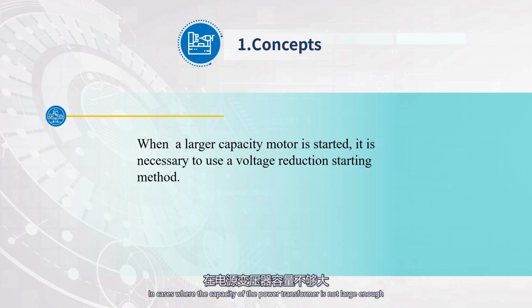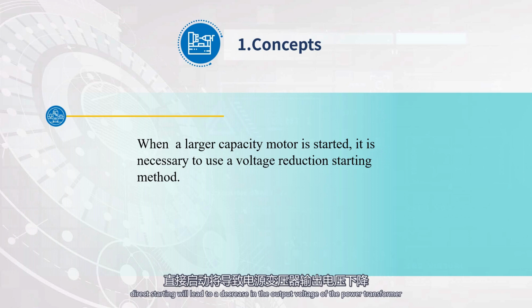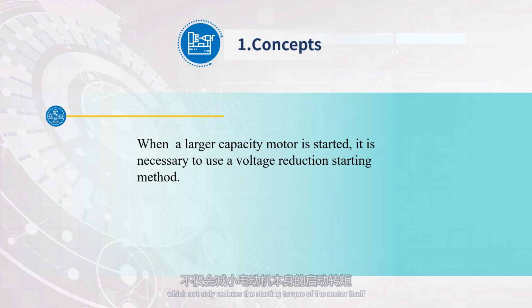In cases where the capacity of the power transformer is not large enough and the power of the motor is high, direct starting will lead to a decrease in the output voltage of the power transformer, which not only reduces the starting torque of the motor itself, but also affects the normal operation of other electrical equipment in the same power supply line. Therefore, when a larger capacity motor is started, it is necessary to use a voltage reduction starting method.